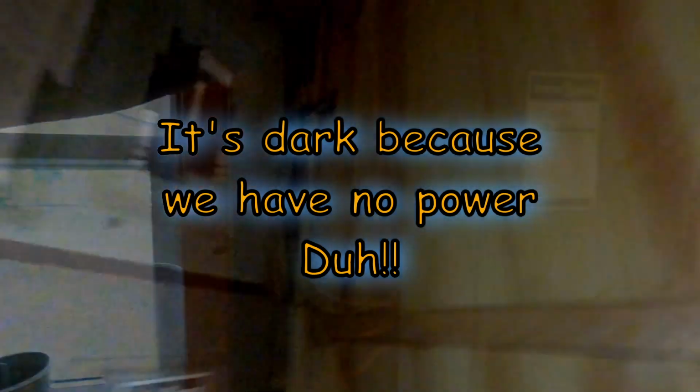Then we take this, apologize for it being so dark here, but first of all I turn off all the circuits in my auxiliary panel, and then this is the transfer switch, so I flip this to generator. Then I put these loads back on, one at a time, each side, balancing the load as much as I can when I turn it back on. You just turn them on and wait 5 or 10 seconds till the generator settles out.